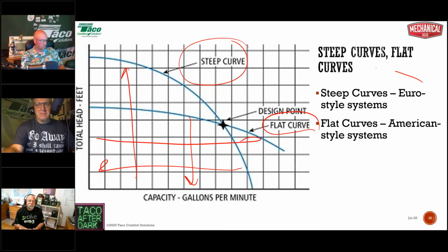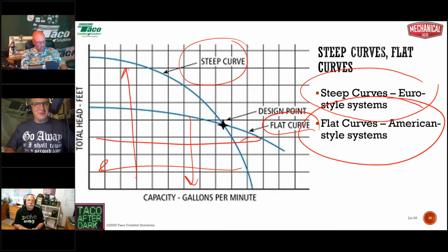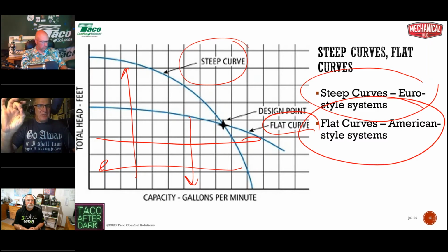So steep curve pumps are called European style circulators, and flat curve pumps are called American style circulators. What we did here in the US is when we had our big building boom after World War II, we were installing hydronic systems into homes as they were being built. All right. They were bigger homes, okay, bigger homes, so higher heating loads. We designed to a 20-degree delta T. We had higher flow rates than if we had a 40-degree delta T. But we're installing the system as the house is being built. We installed larger pipe. So we had higher flow and lower head. In European style systems, they didn't have a big building boom after World War II.